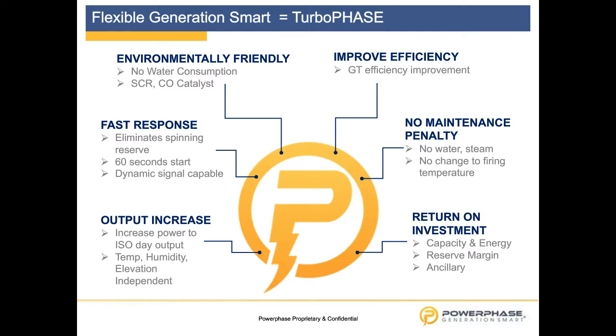We have a positive impact on the efficiency of the gas turbine. As we just inject dry air, there is no maintenance penalty on the main equipment. Combining all of these benefits, we are talking about a fast return on investment. On the capacity and energy side, we increase reserve margin and all the auxiliary power required at certain power stations.